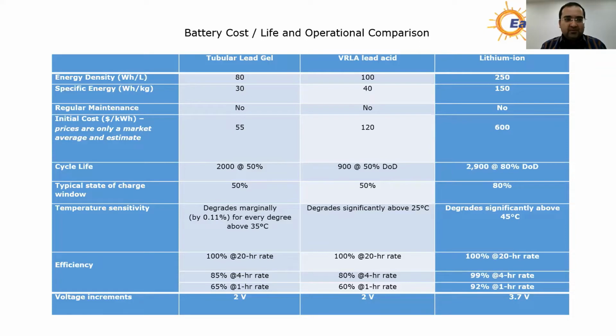If you talk about cycle life at 50% DOD, as of right now, the 2020 onward models are rated at 2000 plus cycles at 50% DOD, as compared to the VRLA, which remains at average 900 to 1000. And the lithium one is higher, at 2900 cycles at 80% DOD, so at 50% DOD this would be somewhere around maybe 4000.